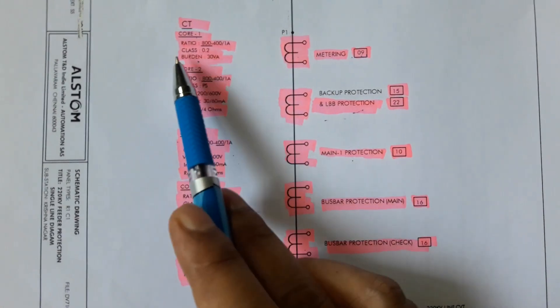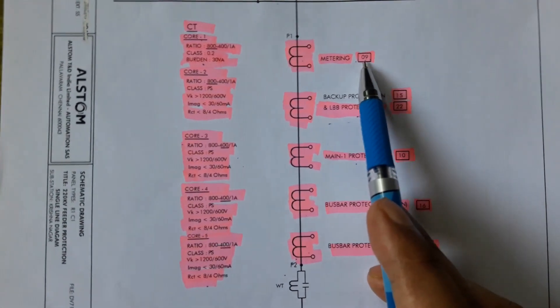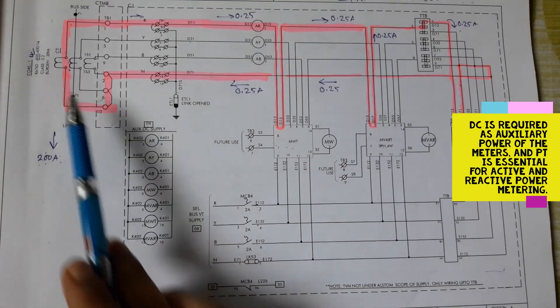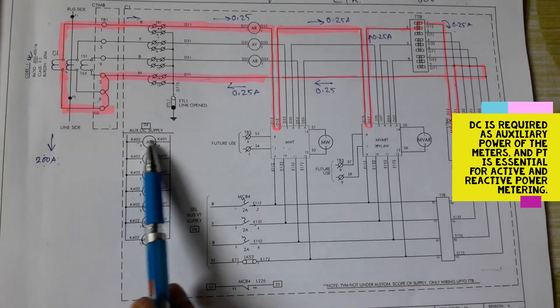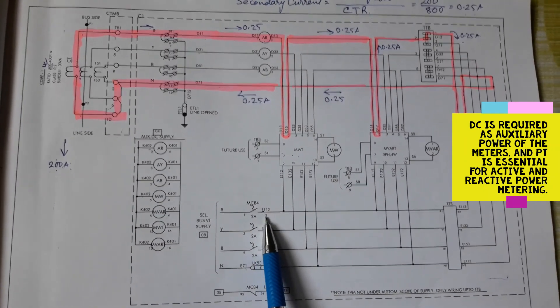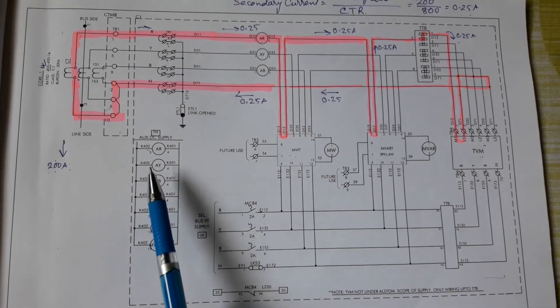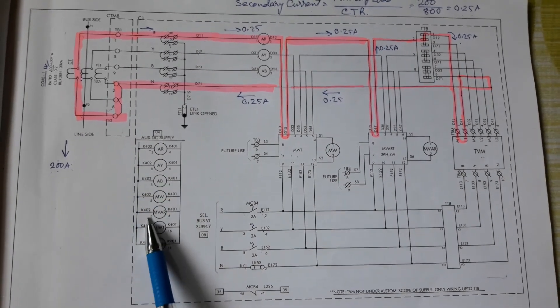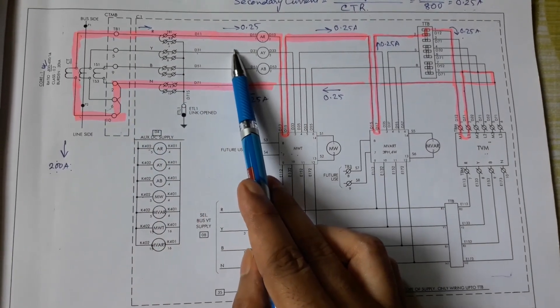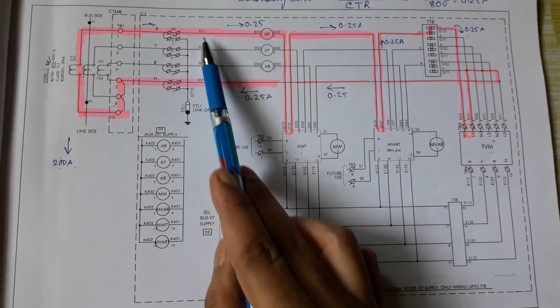Core 1 is the metering core and this metering core is connected with the metering circuit described in sheet number 9. In sheet number 9, besides CT connection, PT and DC connections are also shown. For PT connections, all wire ferrules are prefixed with E; for DC connections, prefixed with K; and for CT connections, specifically for the metering core, all wire ferrules are prefixed with D.